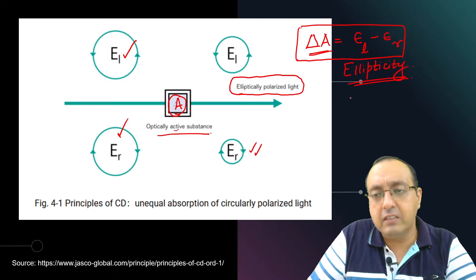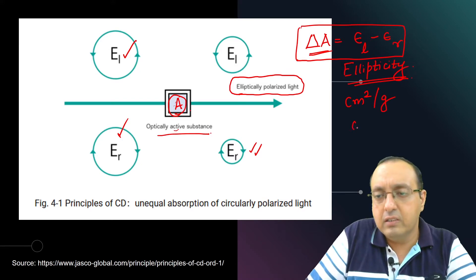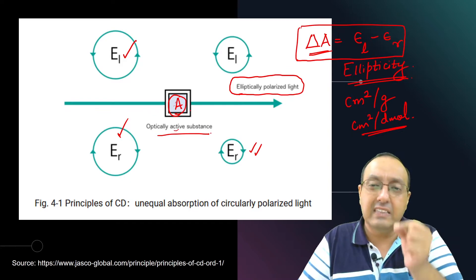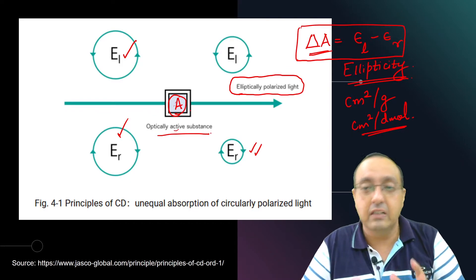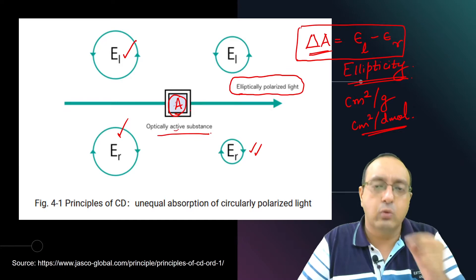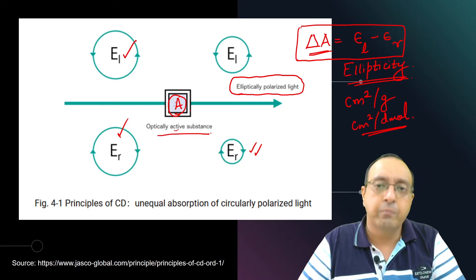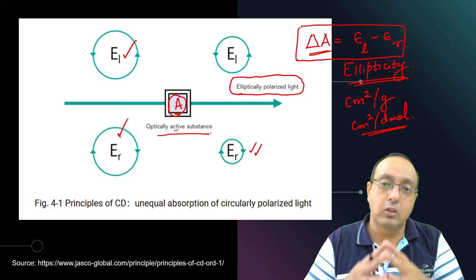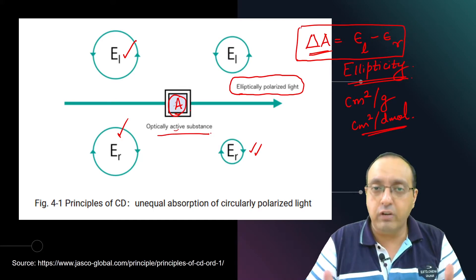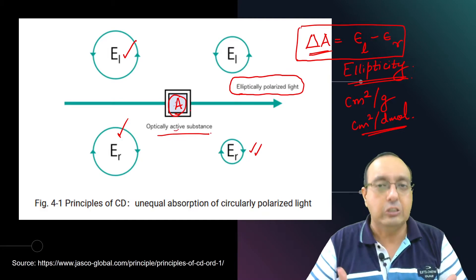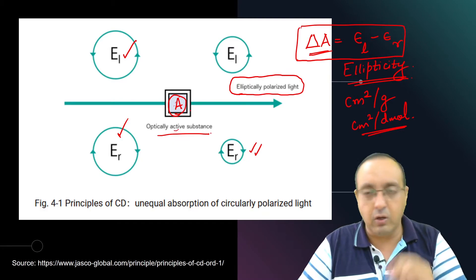This measurement is expressed in the unit of ellipticity, usually in units of centimeter squared per gram or centimeter squared per decimole. It is important to emphasize that these differences are tiny — on the order of 10 millidegrees — so we must be absolutely sure about the difference we are observing. The CD spectrometer is very susceptible to noise.